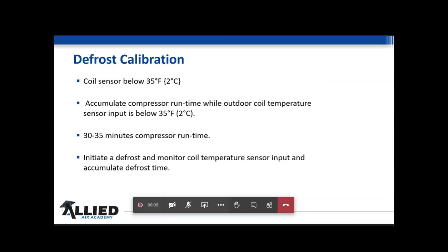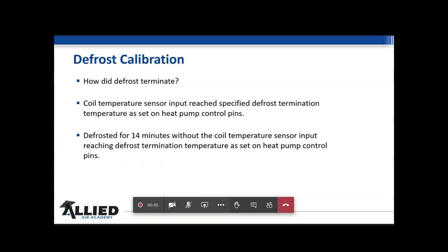So let's look at exactly what needs to happen during a calibration cycle. The coil sensor has to be below 35 degrees. Accumulate compressor runtime with the outdoor coil temperature sensor below that 35 degrees. And then we're going to need 30 to 35 minutes of compressor runtime. And then it's going to initiate a defrost and monitor the coil temperature sensor input and accumulate time. All this I can continue to explain as we go, but just to make sure. So this is part A of that.